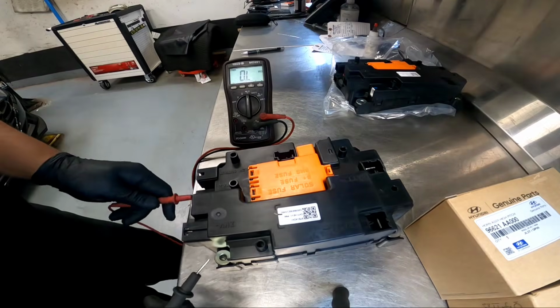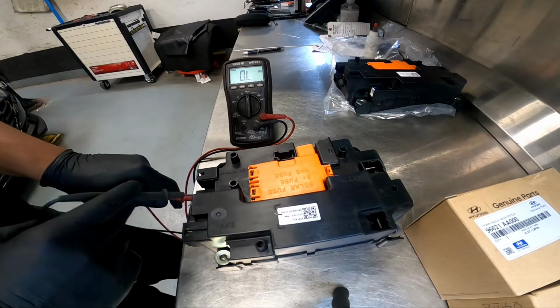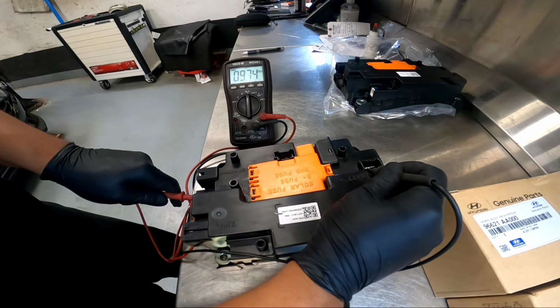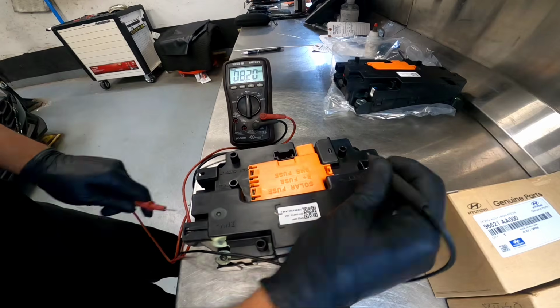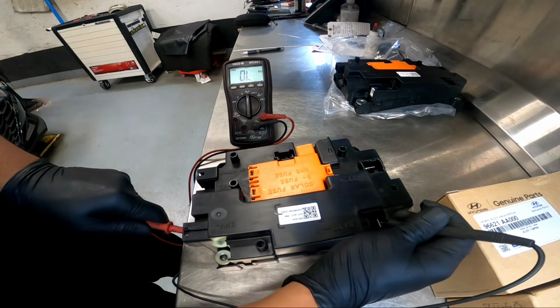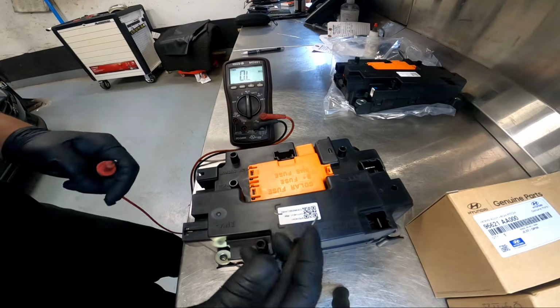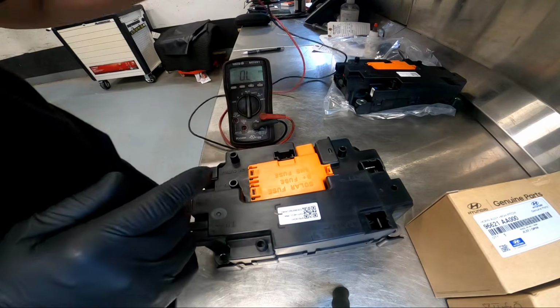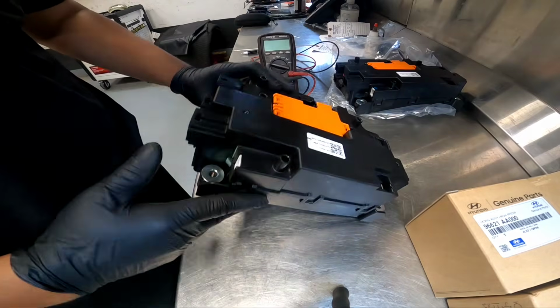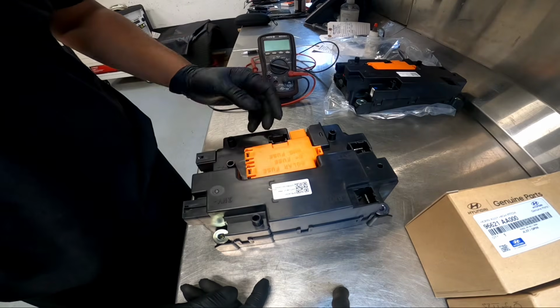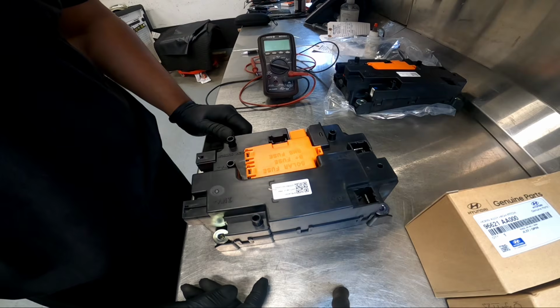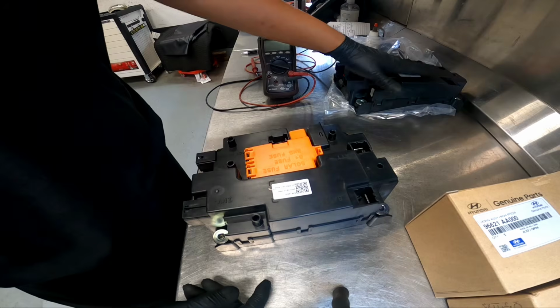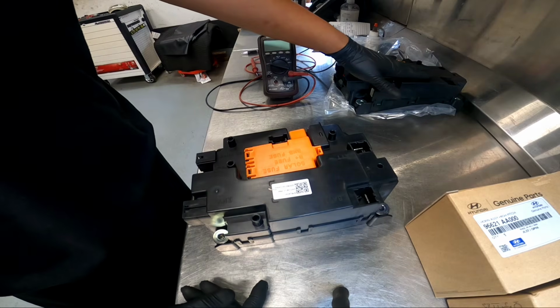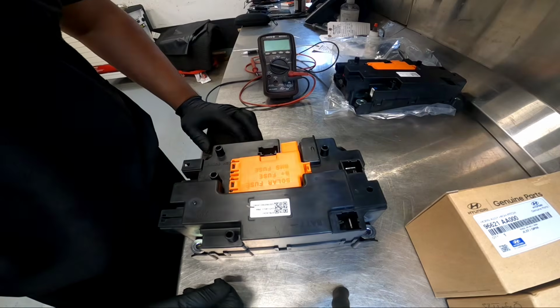And compared to our new one here, same leads, same connection, positive to positive, you should have mega ohms there, or high resistance. As you can see there, you get 8.2 mega ohms. The same thing, negative to negative, reads OL, and this one is reading OL itself. All right, so meaning our switch here is open on the relay side. But my question is, they put specs there that our pre-charge relay should have 40 ohms. But checking that pre-charge doesn't do anything, so just keep that in mind. I guess the pre-charge is mega ohms, I don't know why, but the spec sheet shows 40 at least. But in this case we clearly see the fault, that the relay is closed all the time, right? So we're going to install our new one, and just keep that in mind.